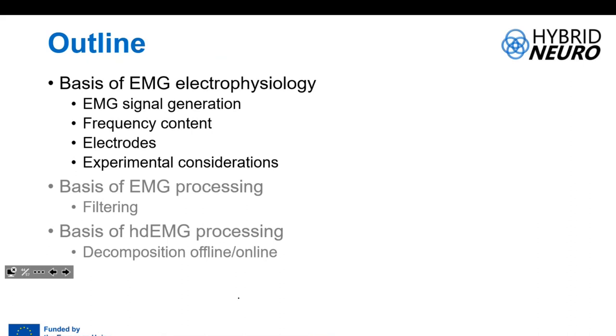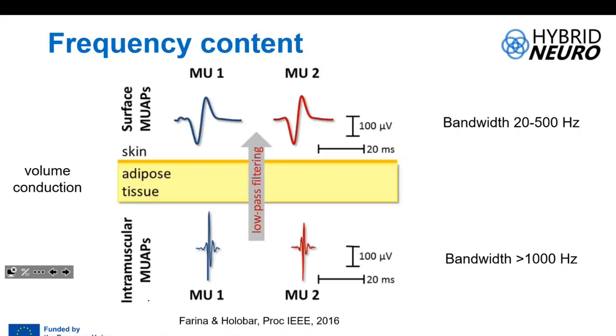About filtering: the bandwidth of surface and intramuscular signals is different, so it's always good to filter the signal in the bandwidth of interest. Below 20 Hz you usually have movement artifacts, and above 500 Hz you have high-frequency noise that doesn't belong to the signal, so you filter it out.